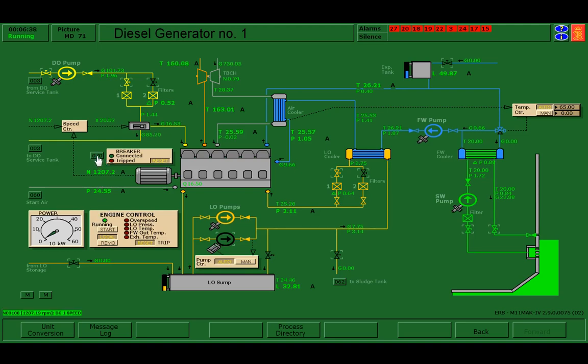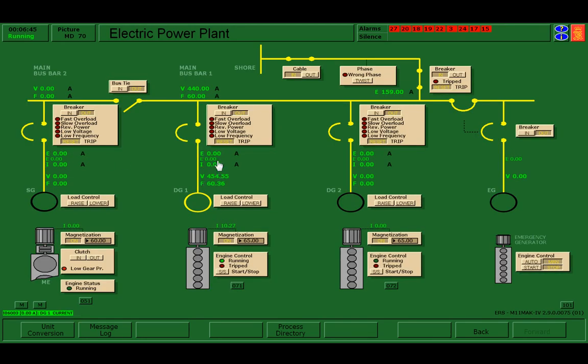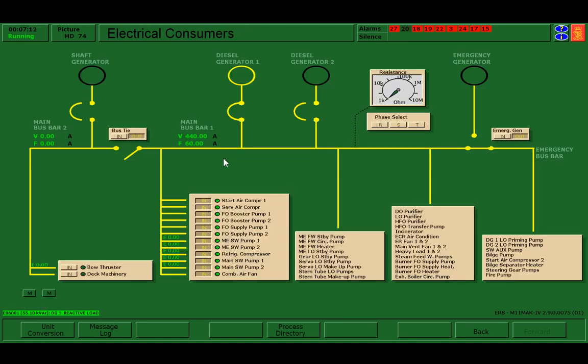Once it's running, I'm going to connect the breaker, so we'll go to page 70. And on page 70, I'm going to connect in my breaker for my diesel generator 1. I want to make sure that it is yellow, so I don't want to connect in a generator that is black and not running. And when I do this, what I'm doing is now producing electricity for my plant from my diesel generator. I could double check on page 74, and my diesel generator is now supplying electricity to almost all components aboard my ship.